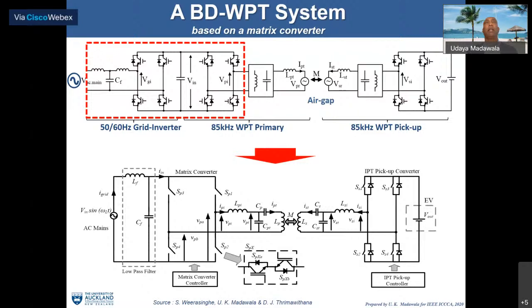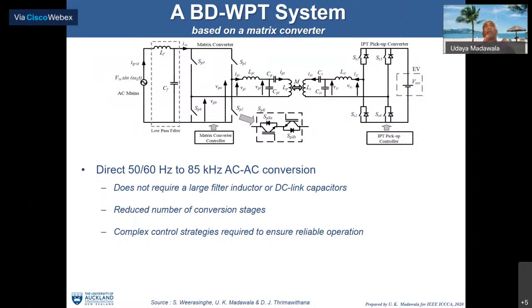We had a complex commutation algorithm, and on top of that there's a resonance circuit. Here's what happens: we take the grid directly at 50 to 60 hertz and convert it to 85 kilohertz. At the time we did this work it was about 25 kilohertz. This approach doesn't require a large filter inductor, reduces the link capacitor, reduces the number of conversion stages, though it requires a complex control strategy as I explained.